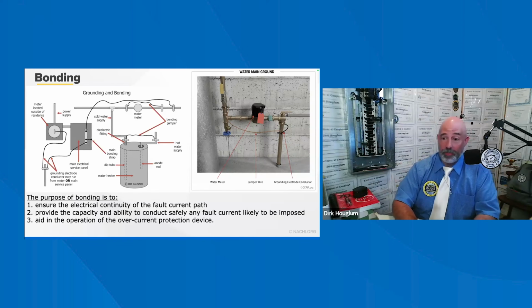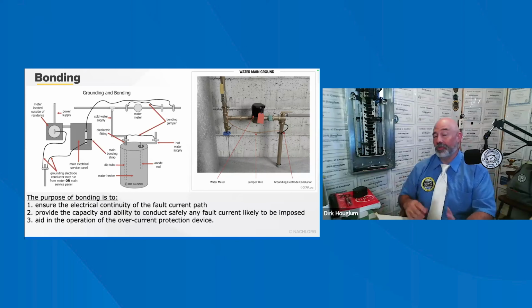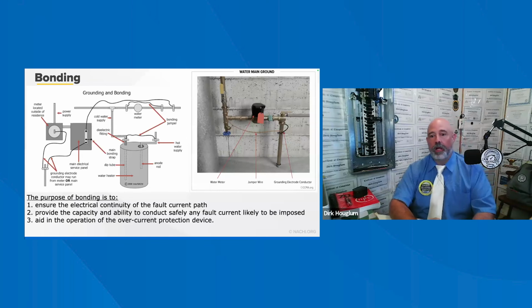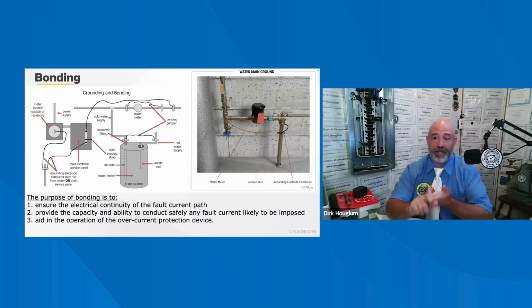Main service panel boards must be bonded to the grounding system, but there is also a very long list of components that need to be connected to the ground since they have the potential to become energized by electrical fault. These components include interior water piping, water heaters, around water meters, gas lines, electrical enclosures, electrical raceways, electrical outlets or junction boxes, CSST gas piping, manufacturer's compliance, of course, and telephone and cable TV systems all have to be there.